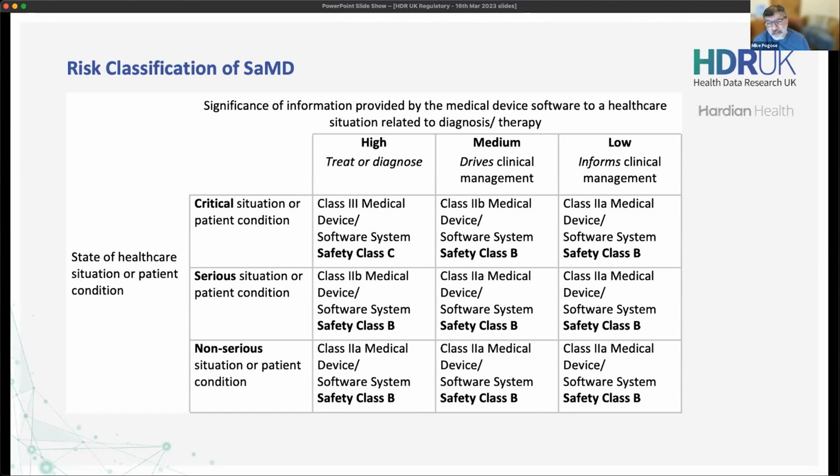There is a very clear part in there that says if you are applying CBT, and it could be any type of similar therapy, ACT or anything, where you're actually claiming to treat and improve someone's mental health condition, you're a medical device. So I hope from that explanation of informing, driving, treating or diagnosing, that becomes more clear.